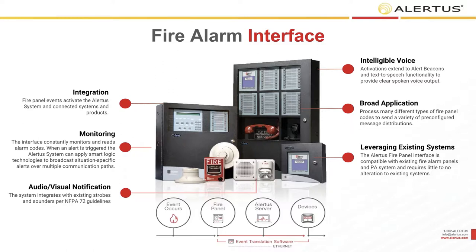Now the heart of things: the fire panel integration. Integration with the fire alarm is a universal integration that uses contact closure — a dry contact — a serial port, and audio line-in. These are all things you can connect to without having to reprogram, change, or recertify your fire panel, which is huge. It's very simple and straightforward.